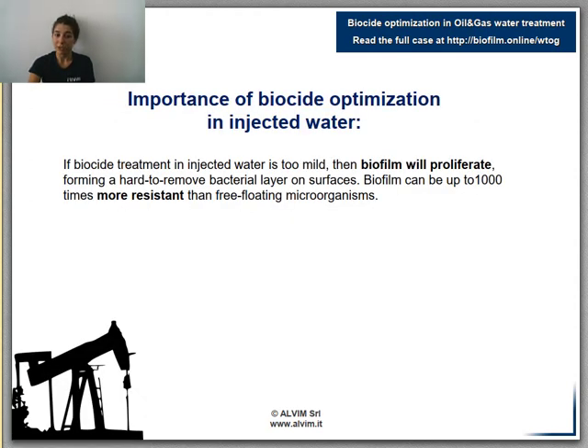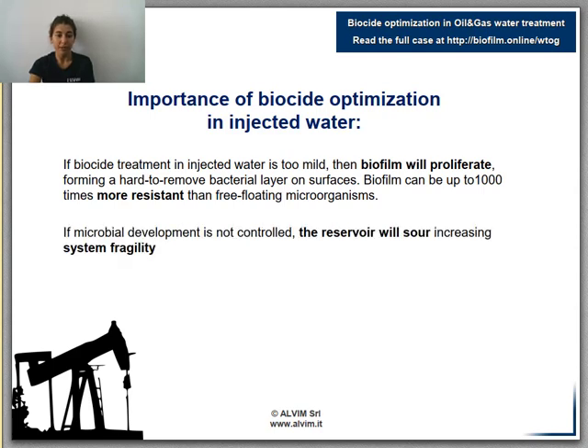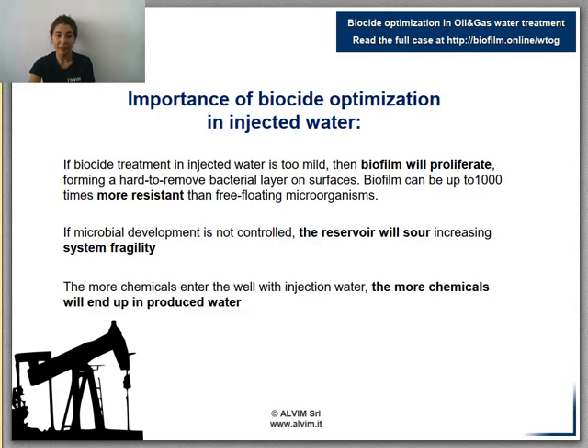Biocide optimization is fundamental because if the biocide treatment cannot keep bacterial growth under control, then biofilm will proliferate. Moreover, the presence of anaerobic bacteria in seawater generates reservoir souring, which increases system fragility. Optimized biocide treatment is also essential because the more chemicals are dosed, the higher the efforts and costs to eliminate them later in the produced water.